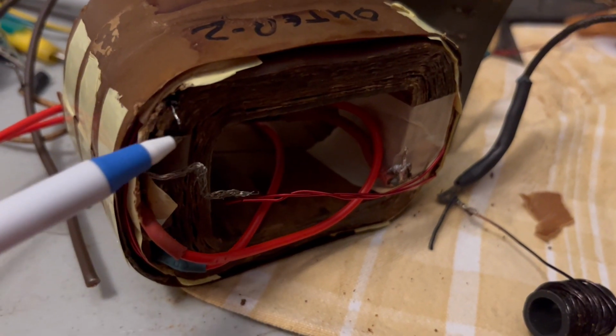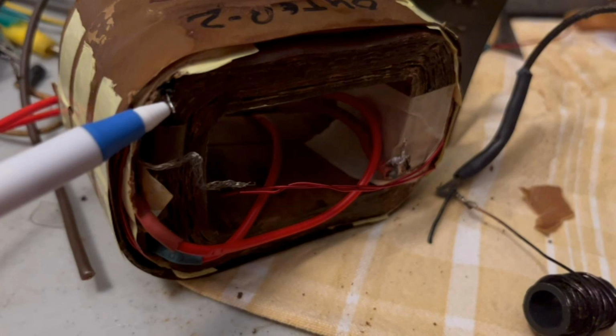And where it's located is right here. Now, although this wire break seemed at the time to be a catastrophe, I would later come to view it as something of a huge stroke of luck, because if it hadn't been for this break so close to the core, I wouldn't have discovered that a much worse issue had occurred at the same time that the short cleared. As it turned out, the HV coil had also gone open simultaneously, and undetected by me because I was focusing entirely on clearing the short. It now seems that when the short cleared, it also opened up the HV coil. And the wire breaking where it did was a completely incidental occurrence that was unrelated to any of the other issues. I guess it helps to have angels on your shoulders at times. A real catastrophe would have been putting that entire thing back together, only to find that it didn't work.